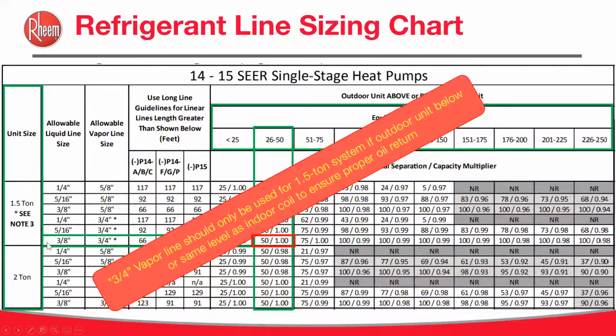But remember I was talking about that asterisk? Well, here it says, asterisk, 3/4 inch vapor line should only be used for 1.5 ton system if the outdoor unit is below or at the same level as the indoor unit. Otherwise, you're going to go to 5/8. It's always recommended for good oil return to go with your smallest suction line available, as per the charts, not what's on your truck or what you're going to pick up, which is cheapest or most cost effective.